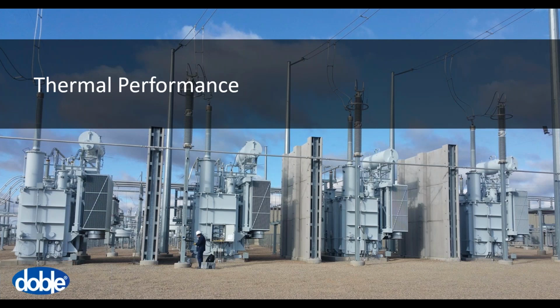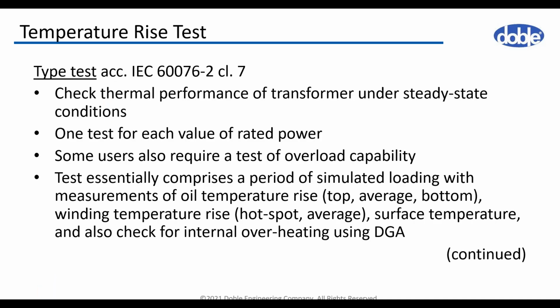So in the next slide, we will be talking about the performance and temperature rise test in particular. Temperature rise test is a type test, and the procedures for determination of temperature and temperature rise values during factory testing are described in IEC 76 part 2, item 7. The purpose of the test is to check the thermal performance of the transformer at steady state condition.